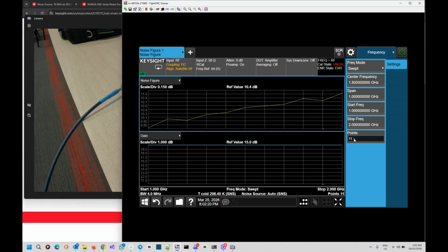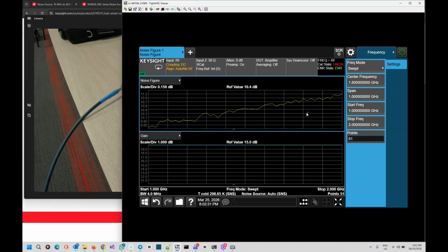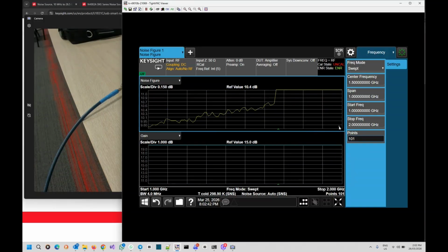The third thing I want to do is change the number of points. For the benefit of this video, I'm going to set it to 51 points. As you can see, when you increase the number of points, it takes a longer time to go through. You can try 101 points and you can see that the sweep time takes a bit longer than with 11 points. You increase the resolution and you increase the sweep time. Let's change back to 51 points because I'm going to change another parameter.